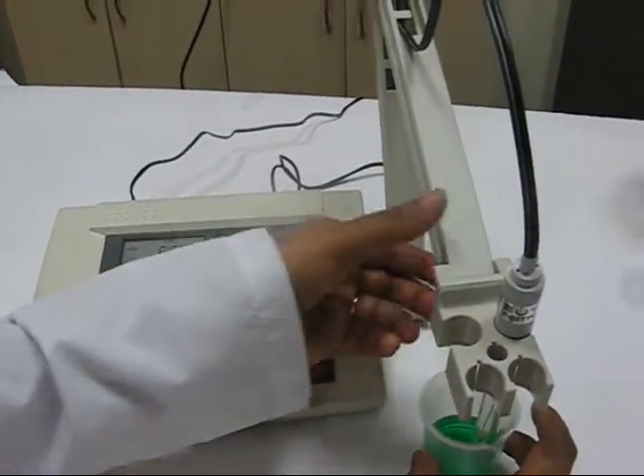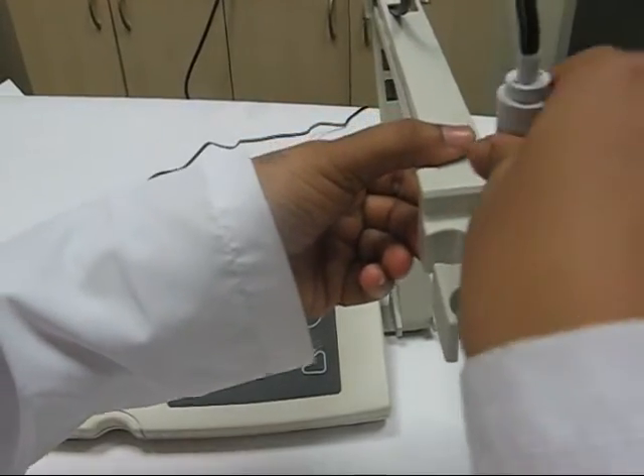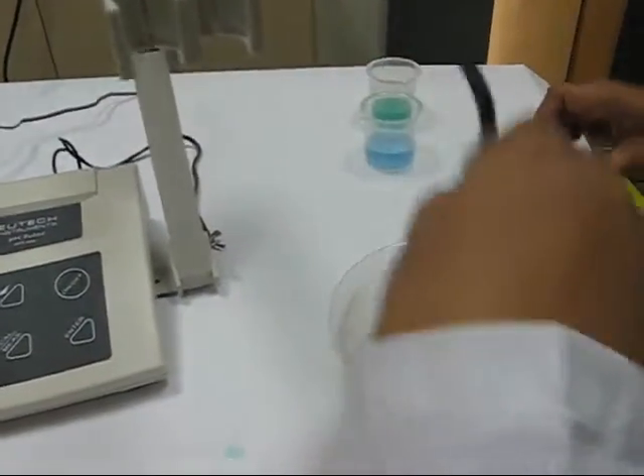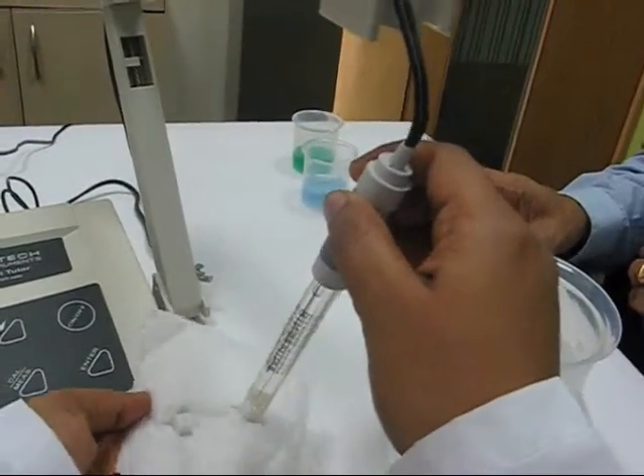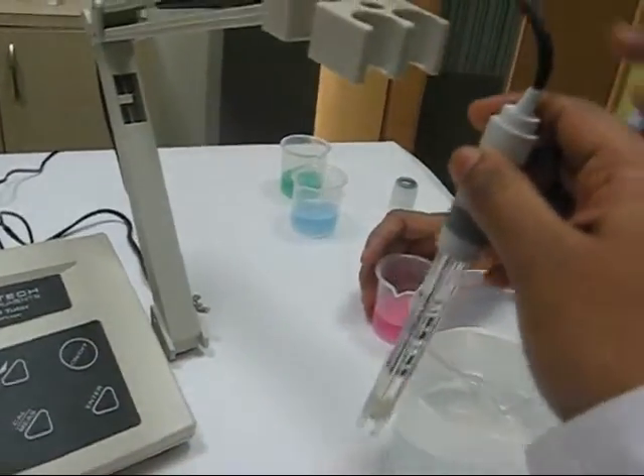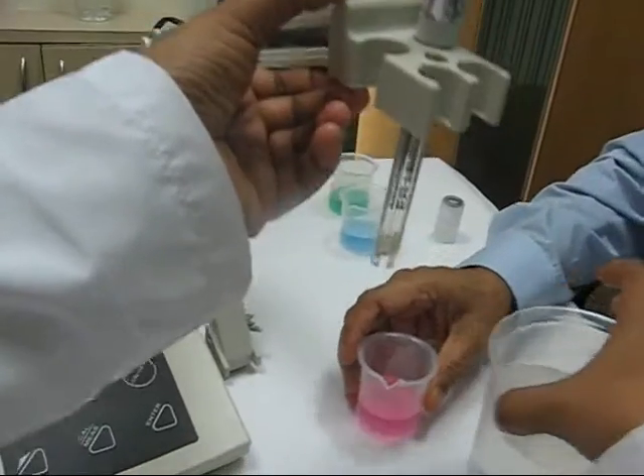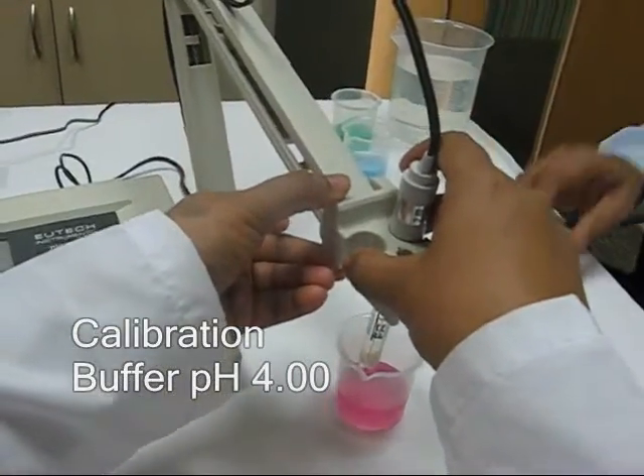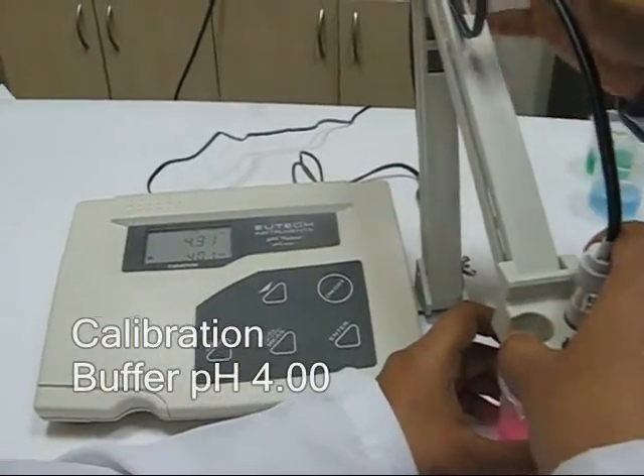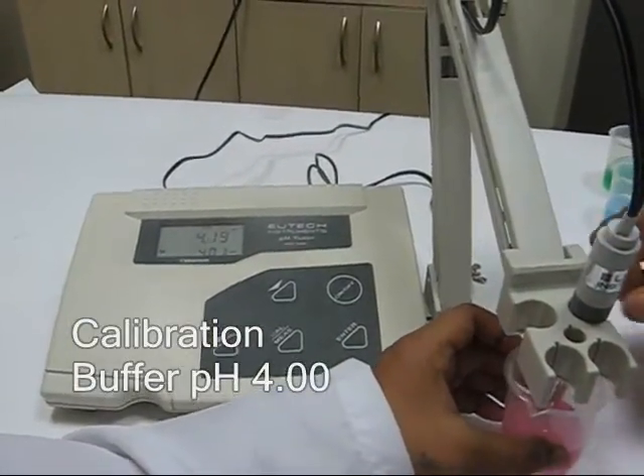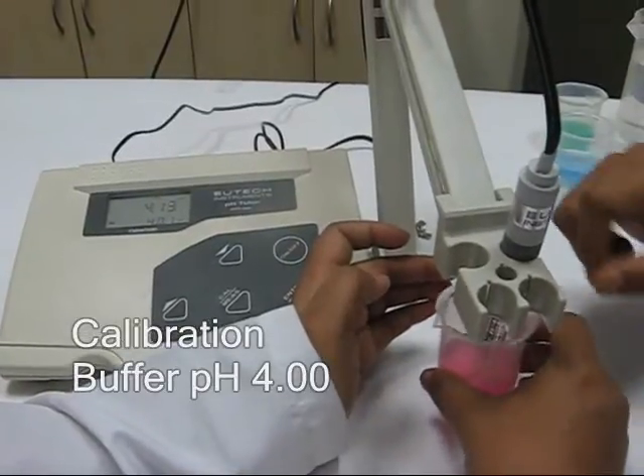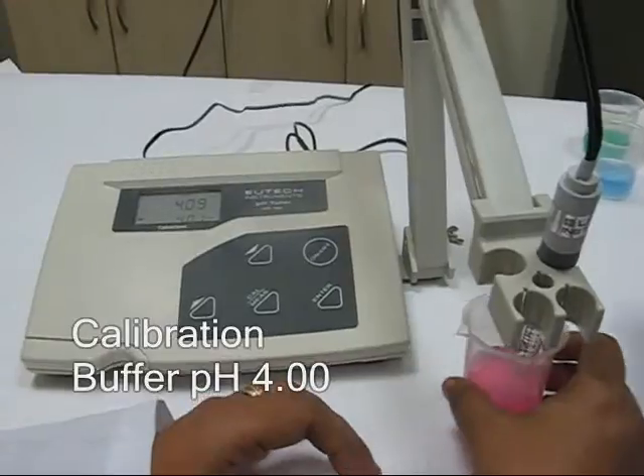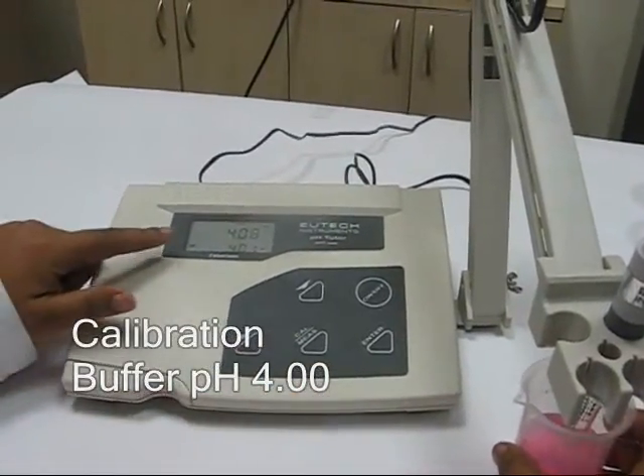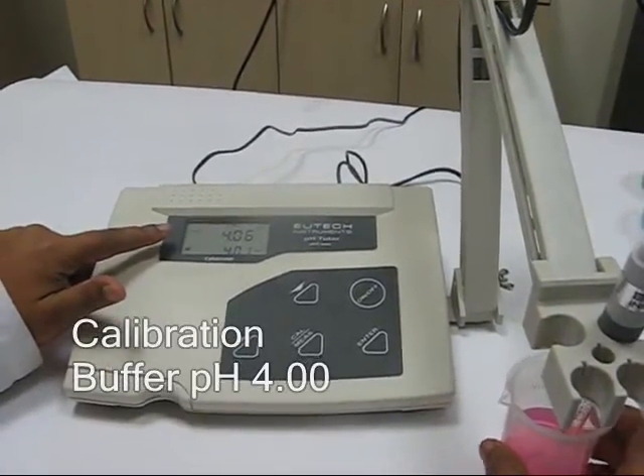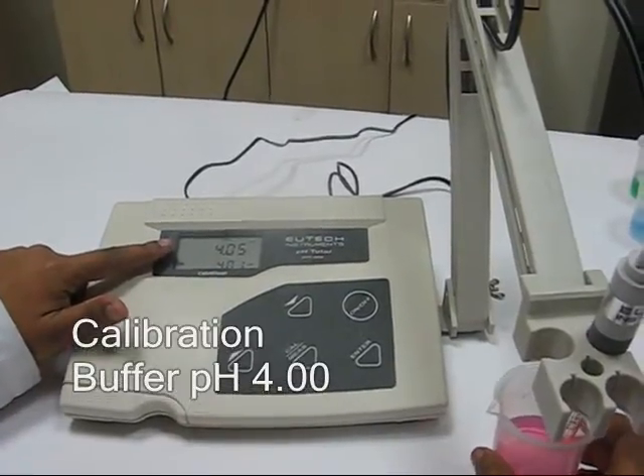Remove this buffer from the electrode. Wash the electrode again well. And we will now look at the second cal point. As mentioned before, just dab it nicely, remove all the water, and we are now ready to do the second point calibration. Usually a gentle mix of the solution is always good, so that you don't have a static sample. Wait for the reading to stabilize. Once the reading comes on, you can press the enter key, and that will confirm the second point calibration.